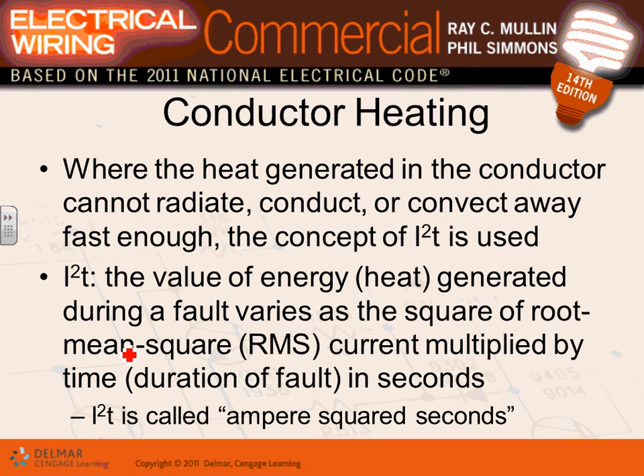I'm repeating myself, guys. There's shaking and baking. The first thing that happens when you have a short circuit or overload condition is heating. The heating is expressed by this term, I squared T. What is I? Current. What's T? Time. I squared T, or I squared S. Take the current squared, multiply by how long, and it gets you how much heat this equipment is rated for. It's called I squared second or I squared time.